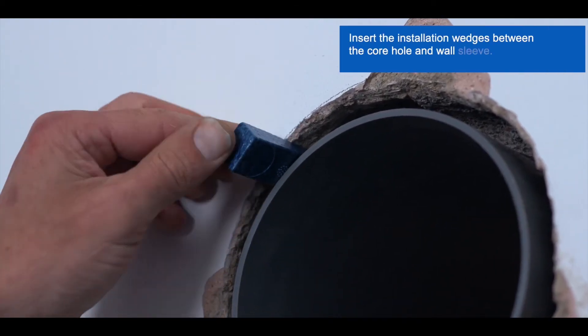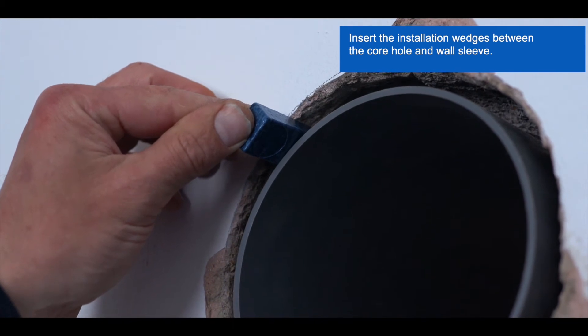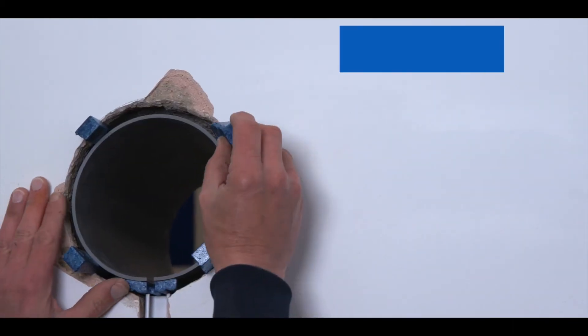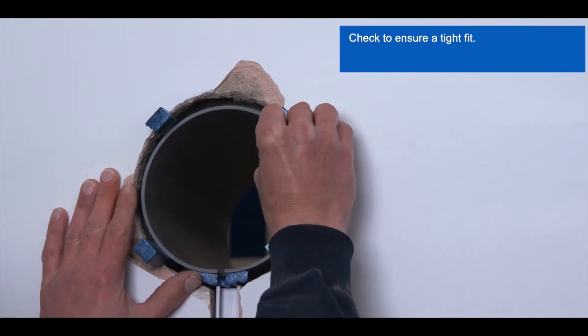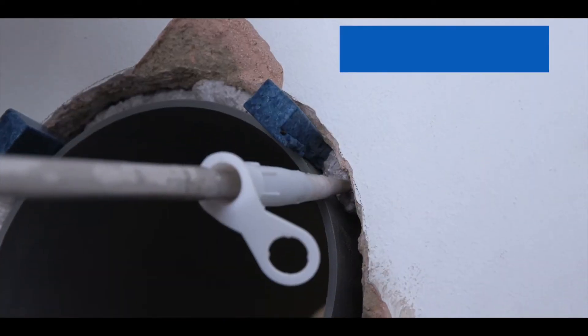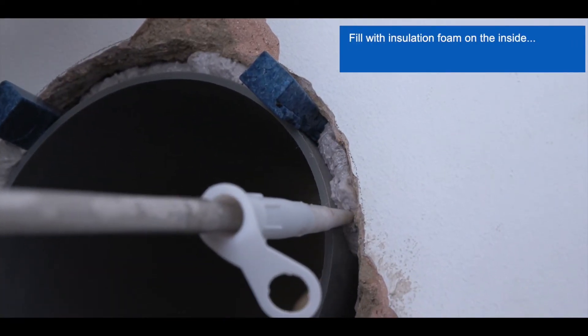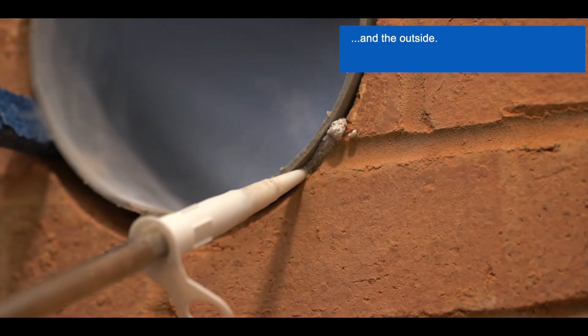Once the wall sleeve is inserted, break up the four installation wedges supplied and insert between the core hole and wall sleeve. Once the wedges have been inserted, check to ensure a tight fit. Fill the gap between the core hole and the wall sleeve with insulation foam on both the inner and outer walls.